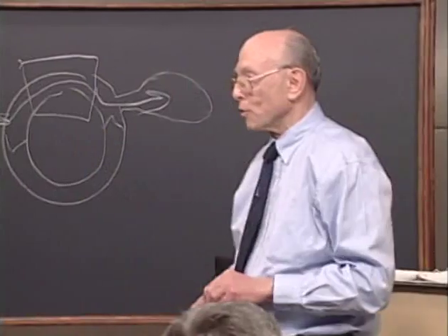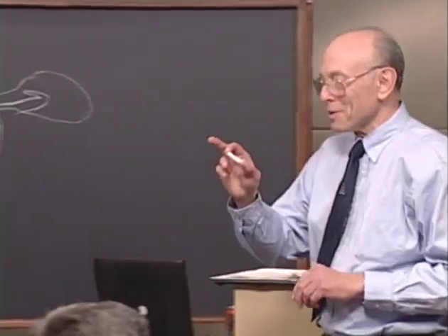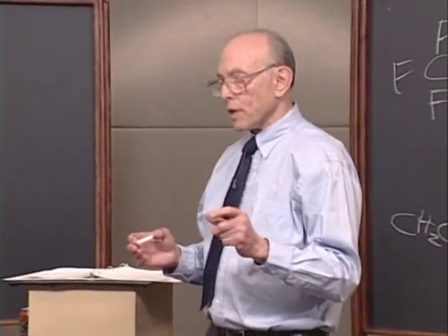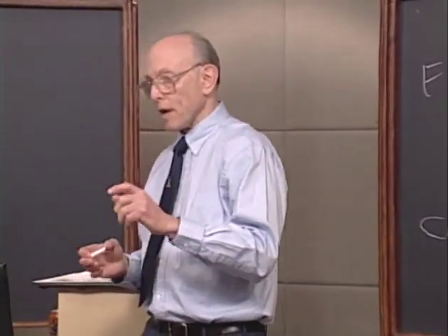I don't know off the top of my head. That's a good answer. It's always a good answer. In fact, there aren't any presently, although there have been suggestions that we would like to have such that would tell us when the absorbent is dry. So we really can't tell. We can tell when the absorbent is exhausted by the change in color, but that's a different phenomenon. So what are we going to do to ensure that the absorbent is not dry?